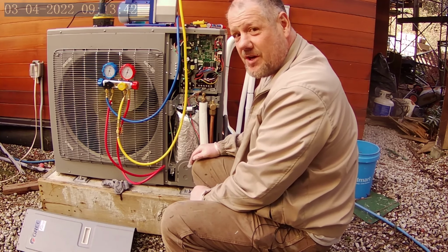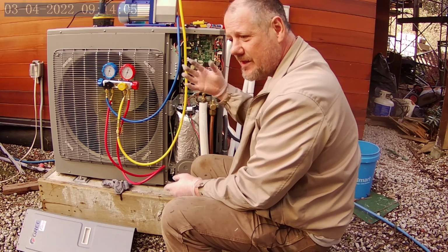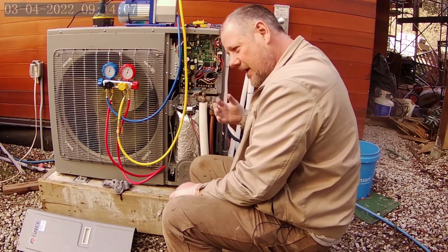So today we're going to start the vacuum process. We want to vacuum it down to 500 microns or lower, and make sure it's stable for a period of time. Then we'll open up the valve to let the refrigerant stored in the heat pump into the line set.